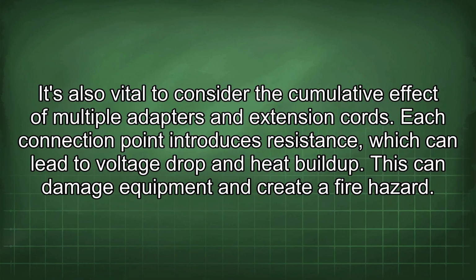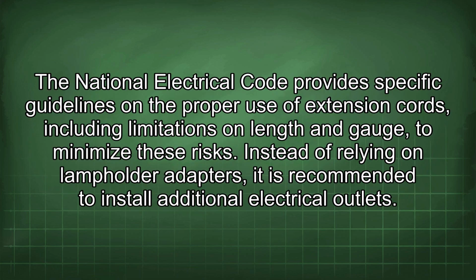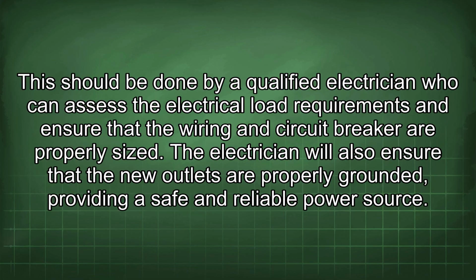It's also vital to consider the cumulative effect of multiple adapters and extension cords. Each connection point introduces resistance, which can lead to voltage drop and heat buildup. This can damage equipment and create a fire hazard. The National Electrical Code provides specific guidelines on the proper use of extension cords, including limitations on length and gauge, to minimize these risks. Instead of relying on lampholder adapters, it is recommended to install additional electrical outlets. This should be done by a qualified electrician who can assess the electrical load requirements and ensure that the wiring and circuit breaker are properly sized. The electrician will also ensure that the new outlets are properly grounded, providing a safe and reliable power source.